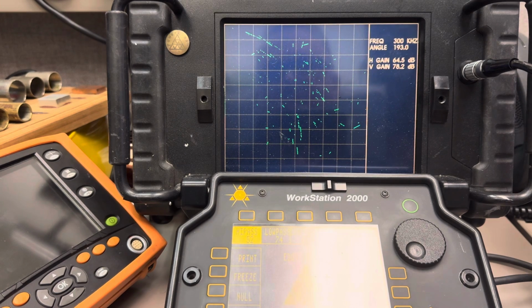find during the test. And how do you know if your test system is adequate to find them? You have a calibration standard using representative types of degradation. You can see them in your cal standard. Then you know that when you go into the actual tubing in your vessel, that you'll be able to calibrate in such a way that if there's degradation in the tubing, you'll find it.